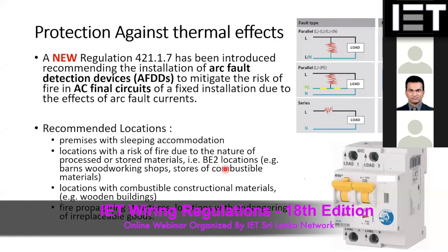And also if you have combustible construction material, like wooden buildings or similar things, then you have to go with arc fault detection devices. And also if there is a location where fire can propagate through the structures, then again you have to use this arc fault detection equipment in those types of locations. This is a new addition.